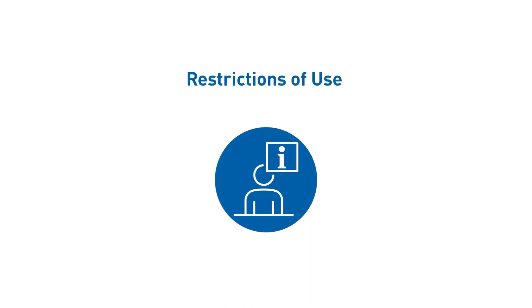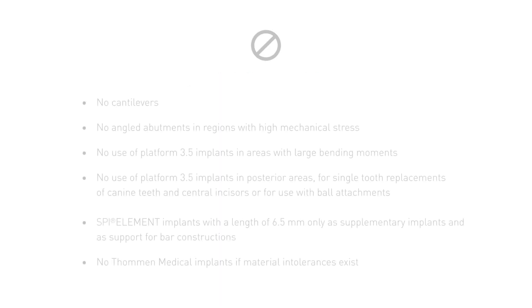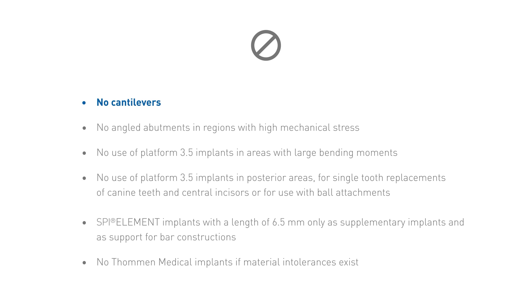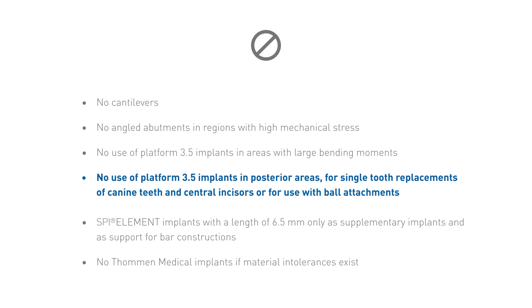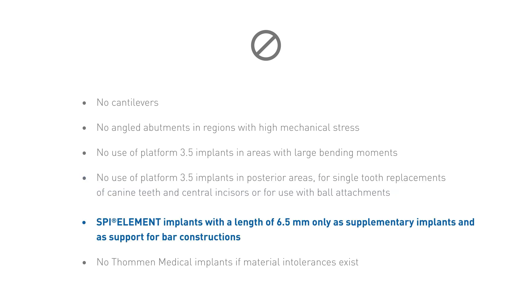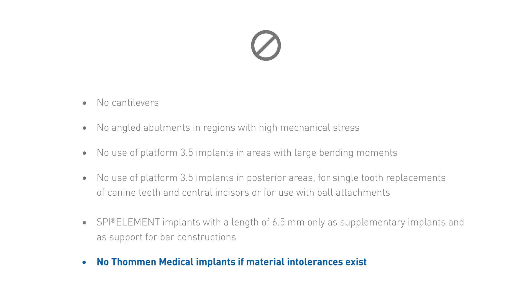Please carefully consider the following restrictions of use for the presented implant system. Thommen Medical does not recommend restorations with cantilevers. Additionally, restorations with angled abutments should not be used in regions with high mechanical stress. When placing an implant with a platform size of 3.5, areas with large bending moments should be avoided. It is further not permitted to use implants with a platform size of 3.5 in posterior areas for single tooth replacements of canine teeth and central incisors, or for use with ball attachments. Element implants with a length of 6.5 millimeters are to be used exclusively as supplementary implants in conjunction with longer implants and as support for bar constructions for full dentures in the lower jaw. Lastly, Thommen Medical implants are not indicated if intolerances to the corresponding materials exist.